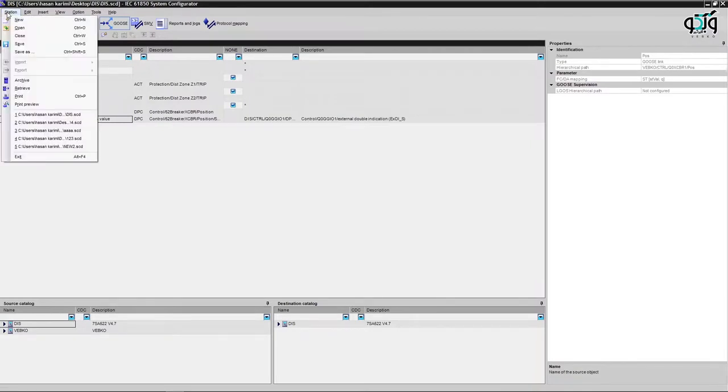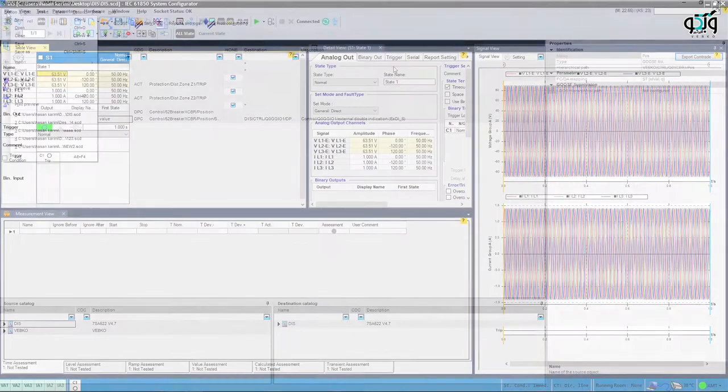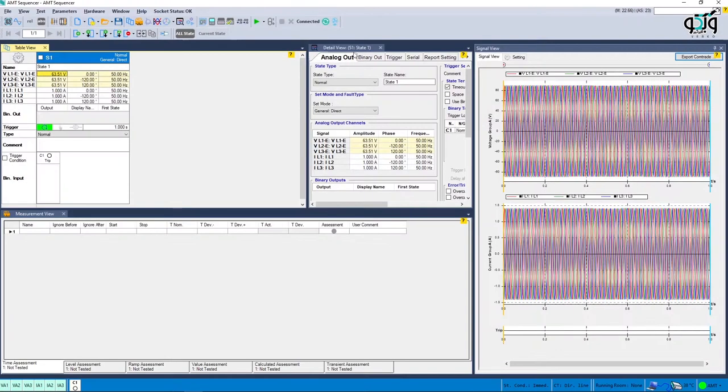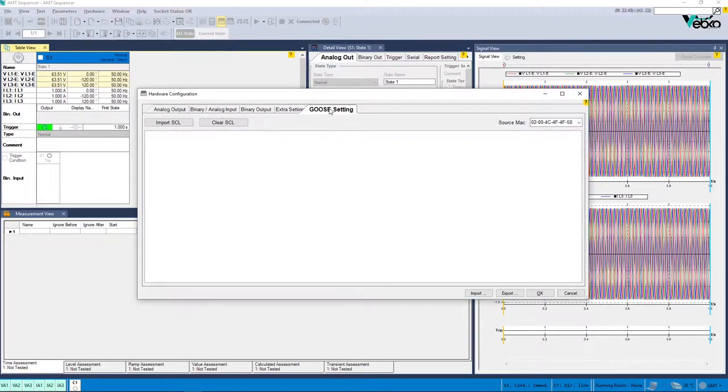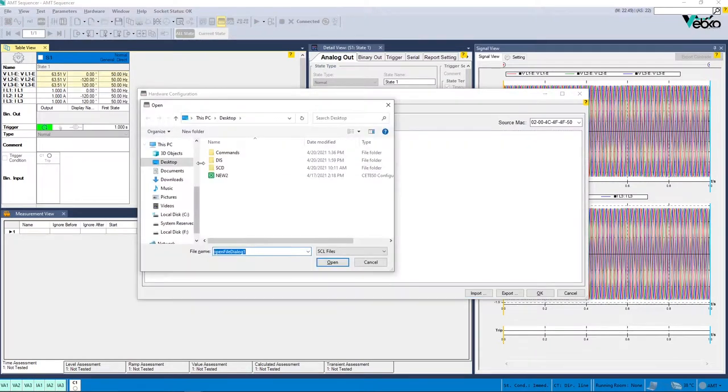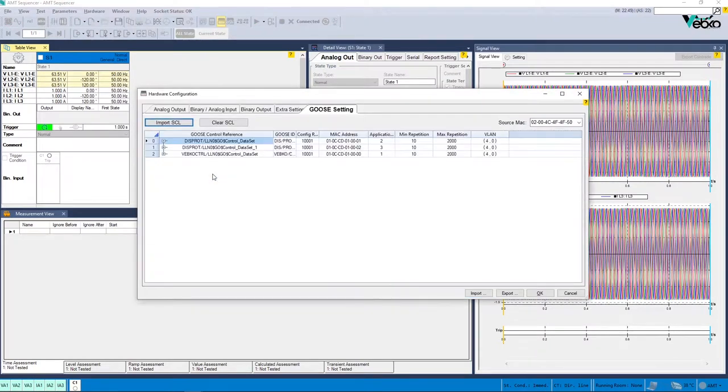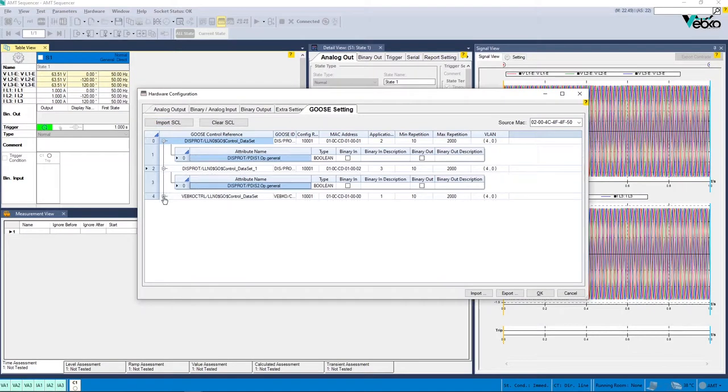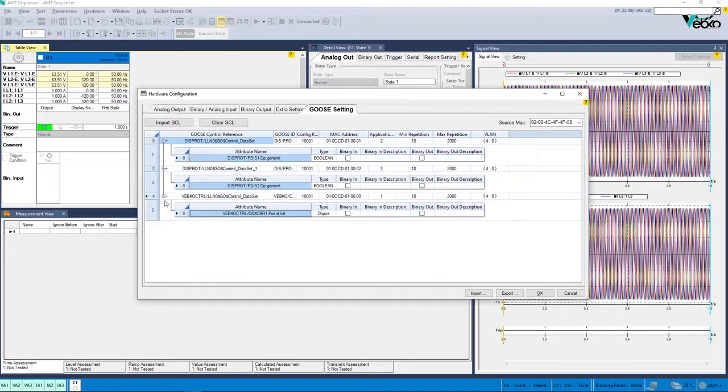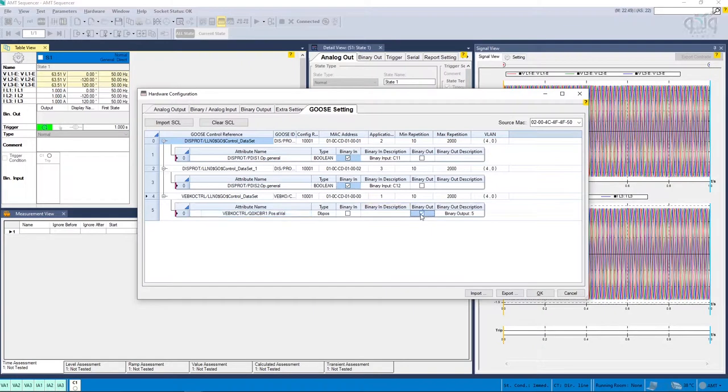In the next step, open the AMT sequencer and click on hardware configuration to go to the GOOSE settings section and import the file saved in the previous step. As you can see, there are three items with subcategories in the GOOSE control reference section. By opening the subcategories, the function of zone 1 is set to binary input 11, and the function of zone 2 is set to binary input 12.